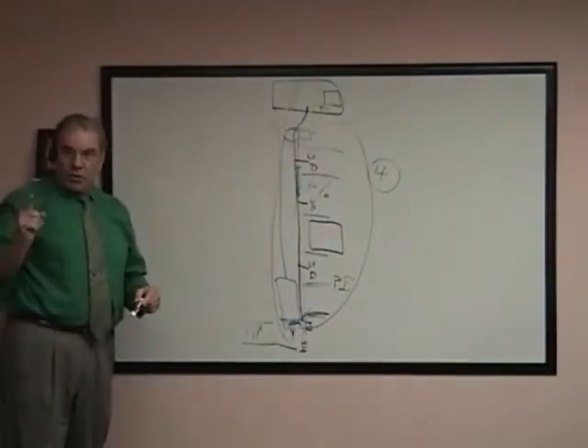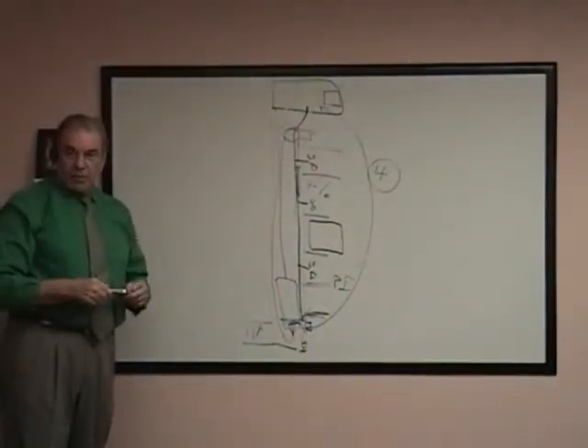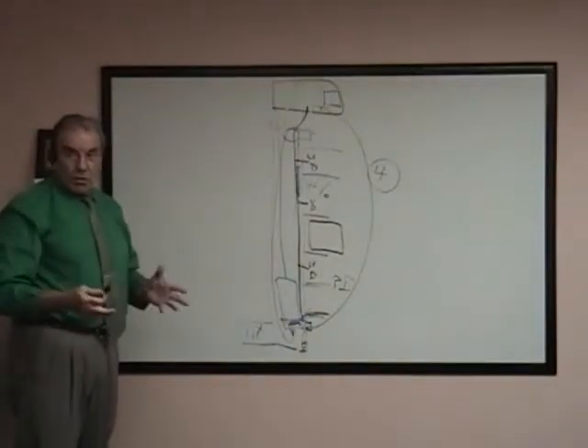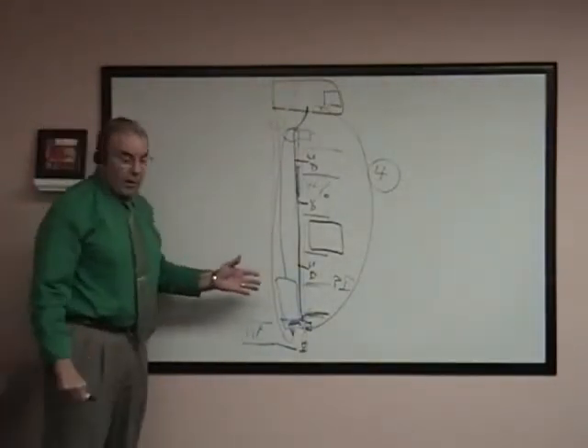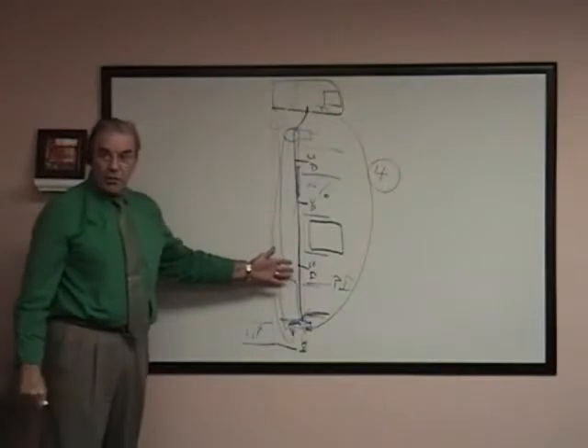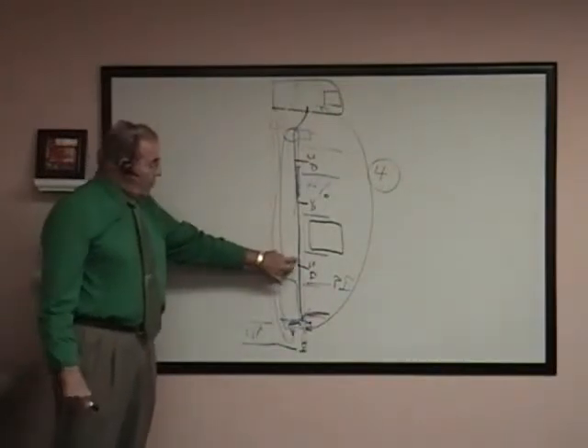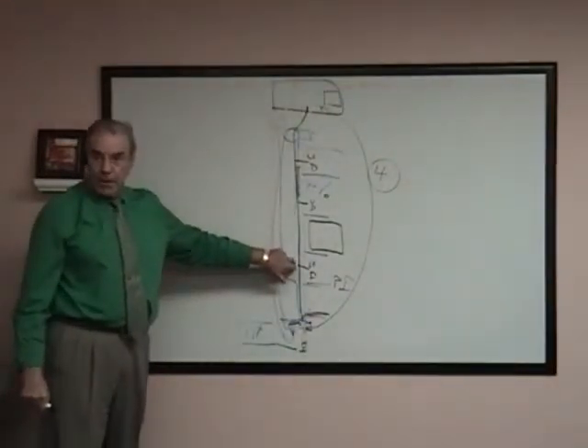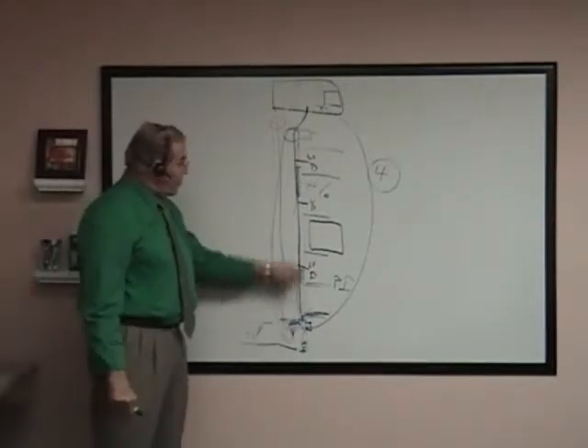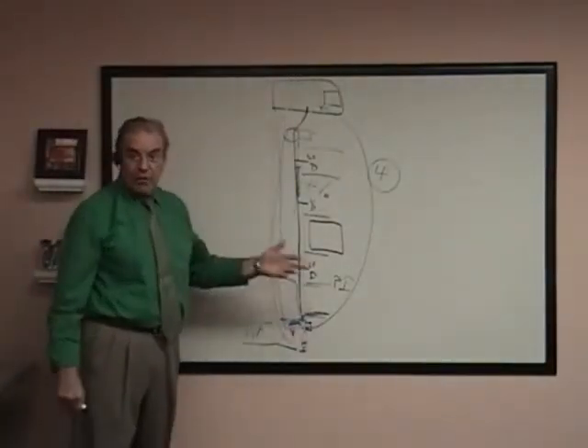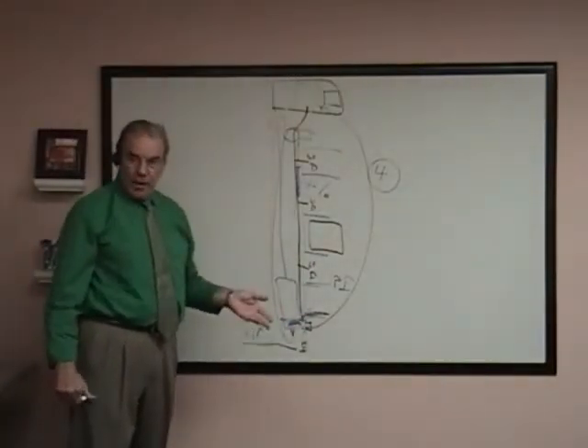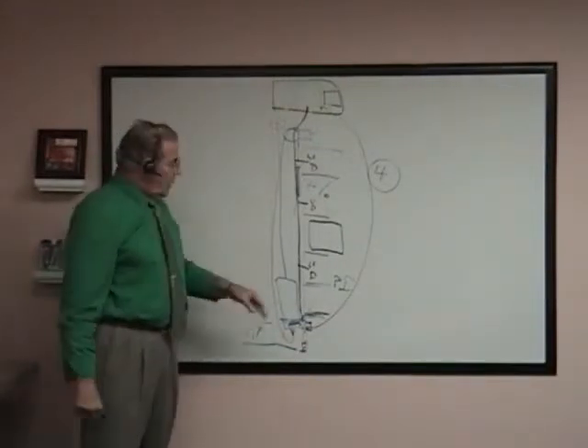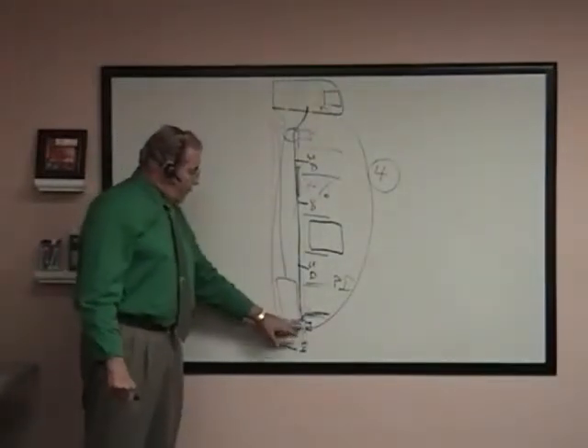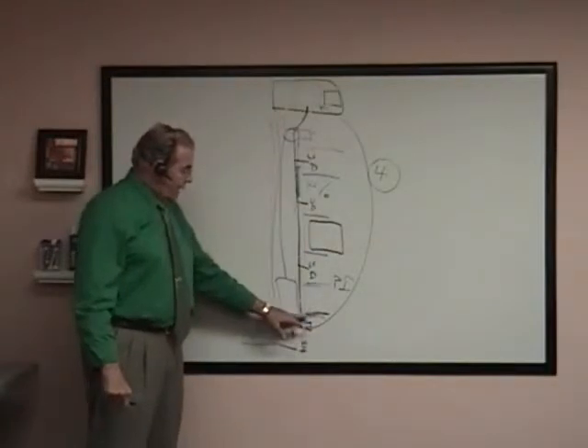If things were installed according to code, code says you have to have 10% spare. So if you had 40 wires, about average for an average hatchway, you should have 4 spares, 10%, and you should be able to use those to do what we have to do. If you don't have spares, then you've got to find them, or get creative. Sometimes you can pick up power from some device already down here.